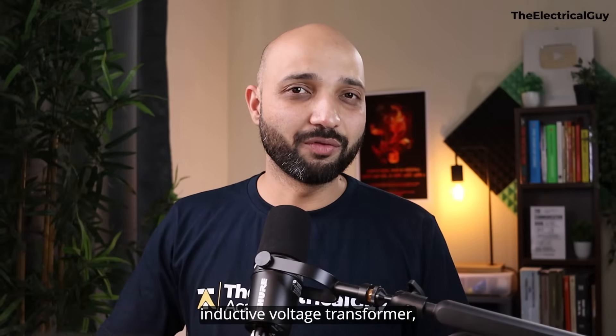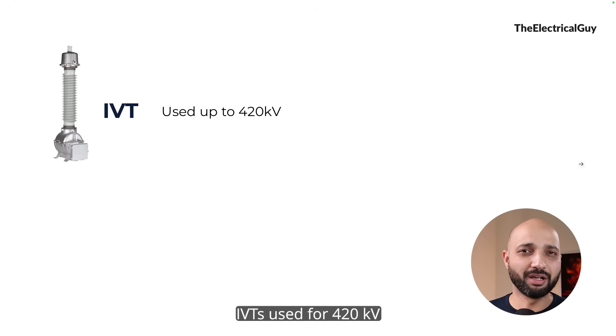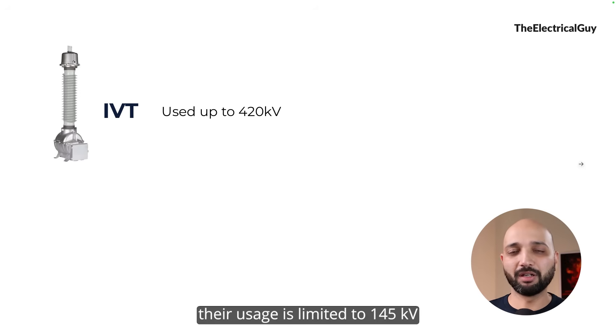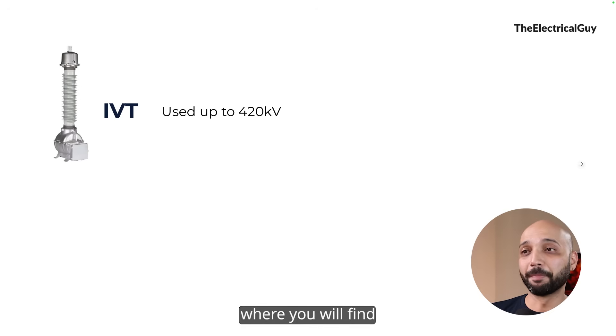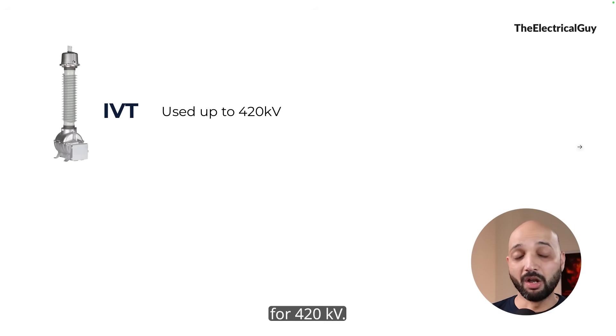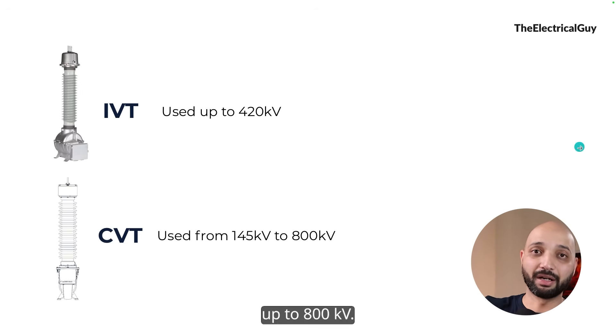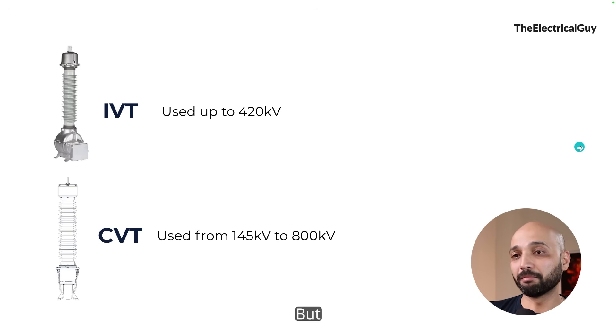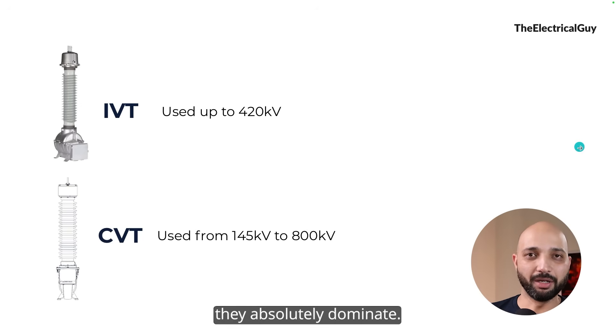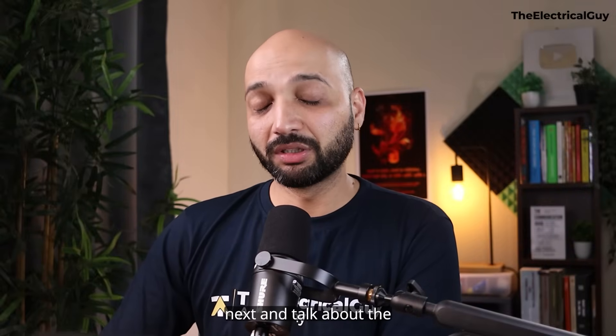Inductive voltage transformers are available up to 420 kV, but you will find very limited applications or substations where IVTs are used at 420 kV. Capacitive voltage transformers, on the other hand, are used from 145 kV all the way up to 800 kV, giving them a wide range of application. For higher voltage classes, CVTs absolutely dominate, while the use of IVTs is limited.